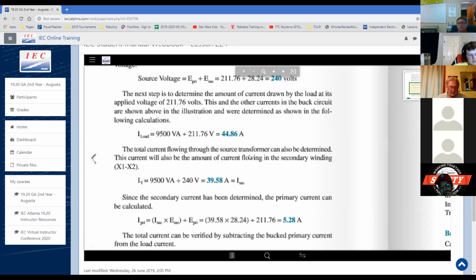So the total current flowing through the source transformer can also be determined. Even with the buck, we still have 240 as the source. That's 9,500 VA divided by 240 volts. That's 39.58. And if you do the buck boost, you take the 39.58 times the 28.24. That's the voltage of the secondary, the buck side, and you divide that by the overall 211.76, and you get 5.28 amps.